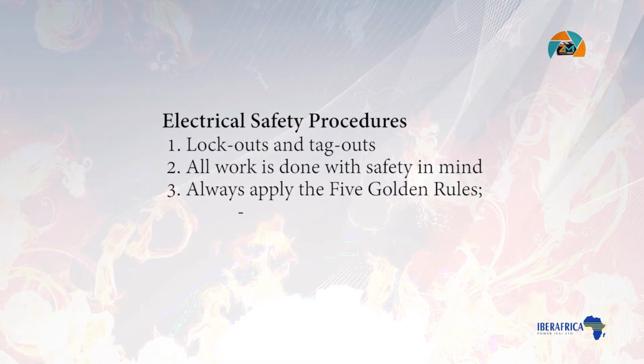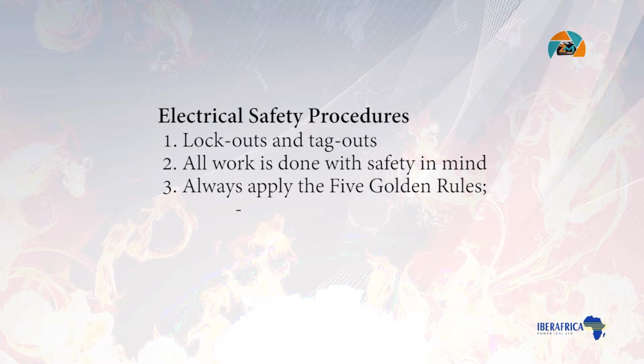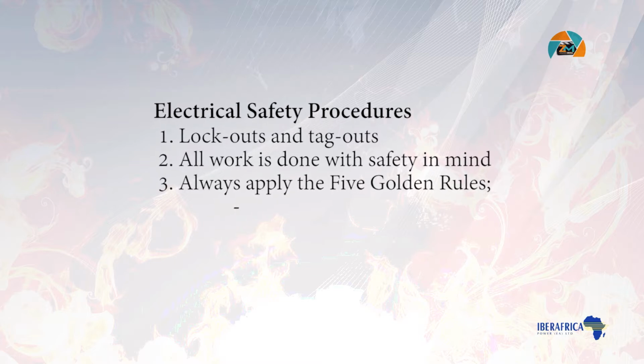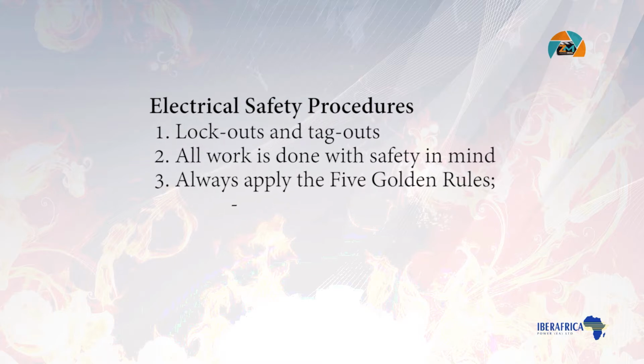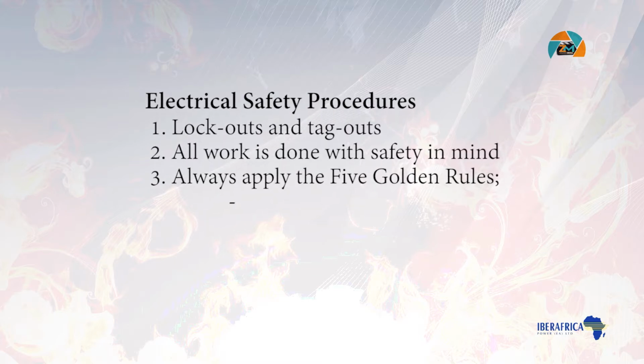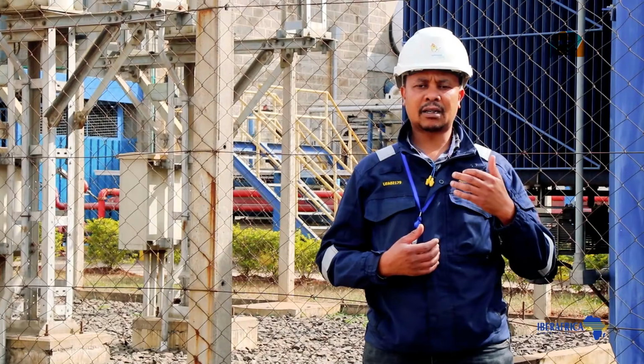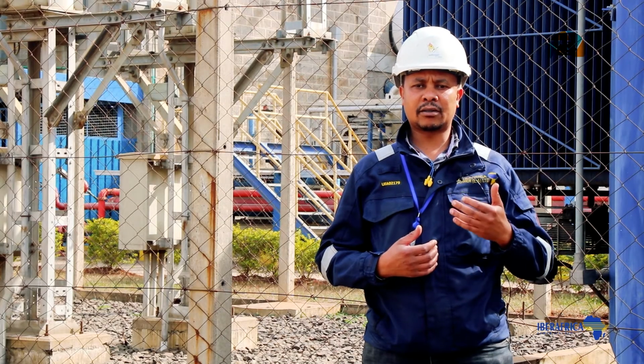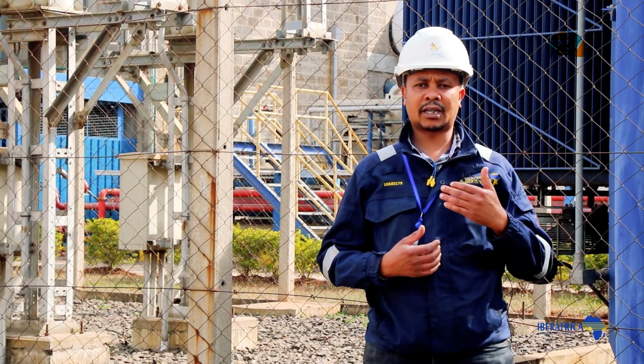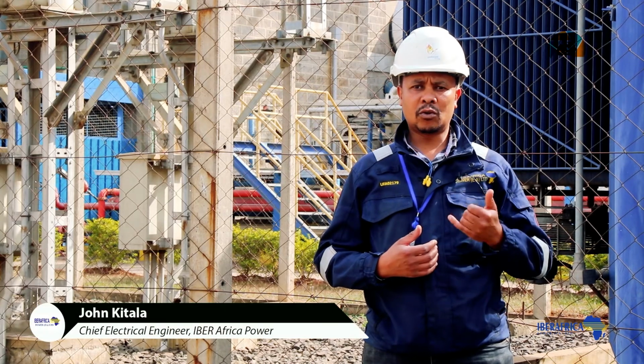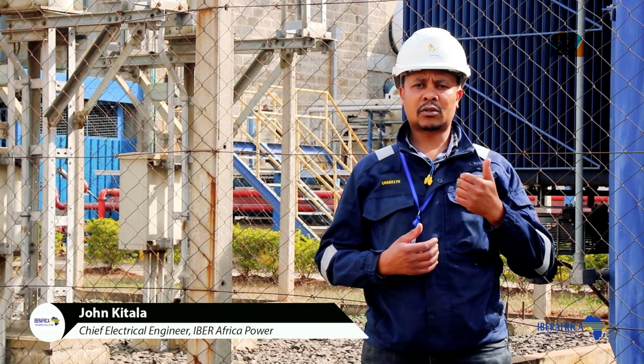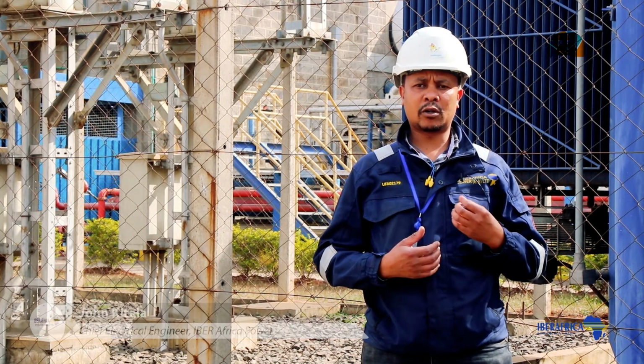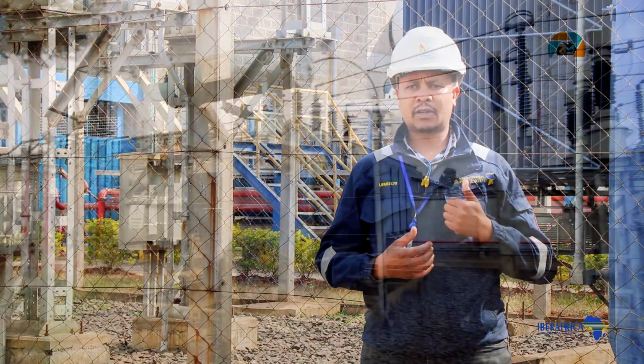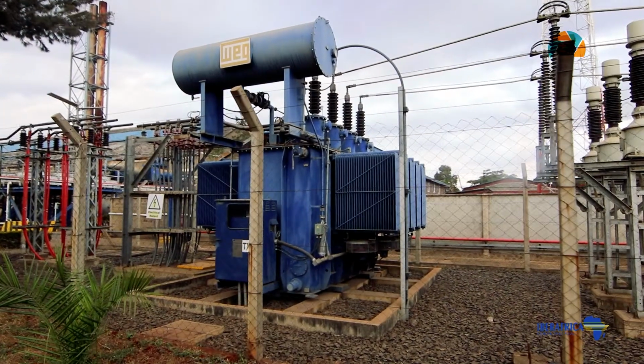We always apply the 5 golden rules. We make sure we don't work on live circuits, and we verify that circuits are completely de-energized. Over and above locking out and preventing accidental energization of systems under maintenance, we do the lockout and tagout, and we also apply the earthing principle to make sure the systems are safe, discharged, and ready for working.